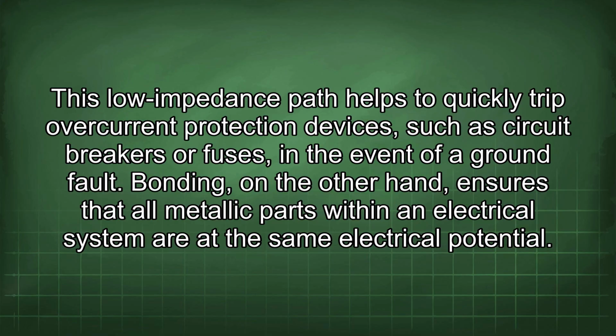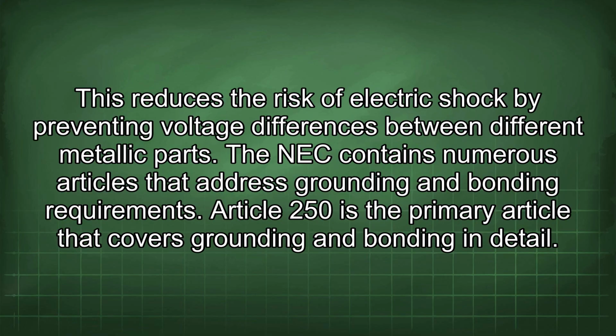Bonding, on the other hand, ensures that all metallic parts within an electrical system are at the same electrical potential. This reduces the risk of electric shock by preventing voltage differences between different metallic parts. The NEC contains numerous articles that address grounding and bonding requirements. Article 250 is the primary article that covers grounding and bonding in detail.